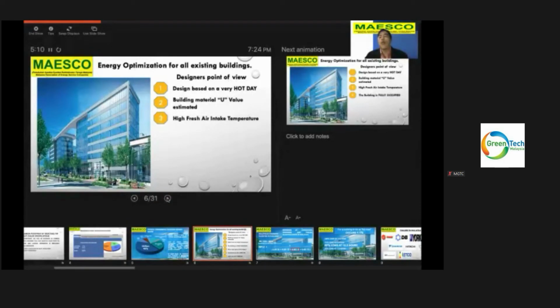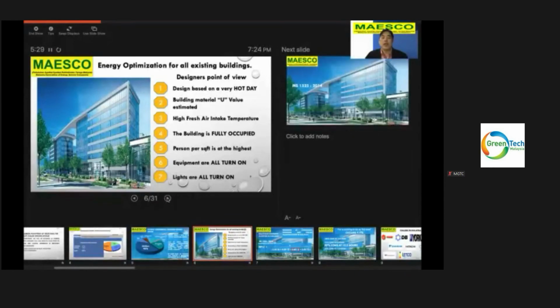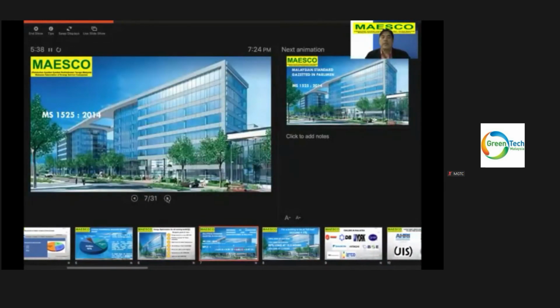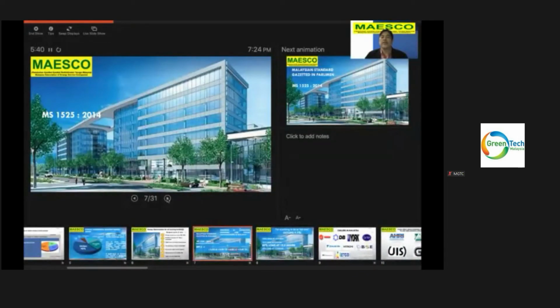And we always put in a high fresh air intake temperature. In Malaysia, we usually base it on 31 degrees C. Our assumption is always that the building is fully occupied, and the persons per square feet is the highest. Number 6, equipment is all turned on. Number 7, lights are all turned on as well. Now, you may ask yourself, how does all this affect you?